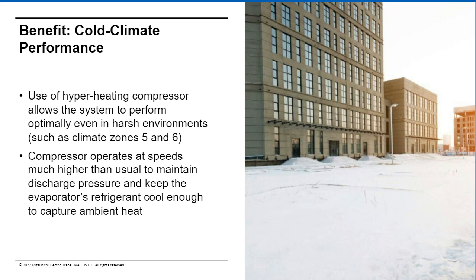This allows the heat pump water heater to produce 176-degree domestic hot water at negative 13 degrees Fahrenheit, but just at a reduced GPM. So the sizing of your storage tanks becomes important in your system sizing, as there needs to be enough storage capacity during drawdown events and enough production capacity during periods of latency. Oversizing of the heat pump water heater system will cause excessive cycling and diminished COP.